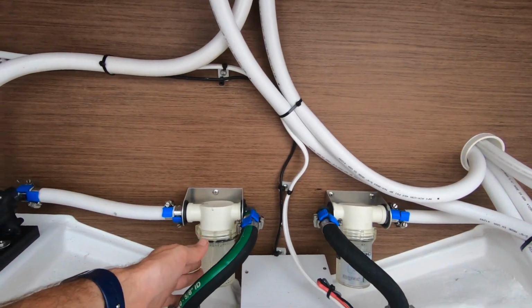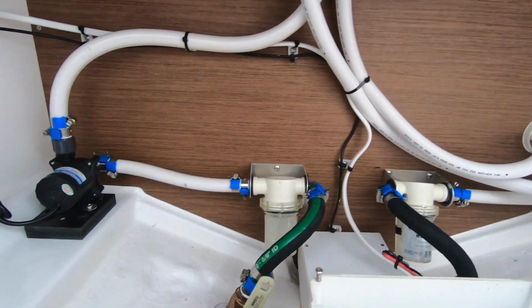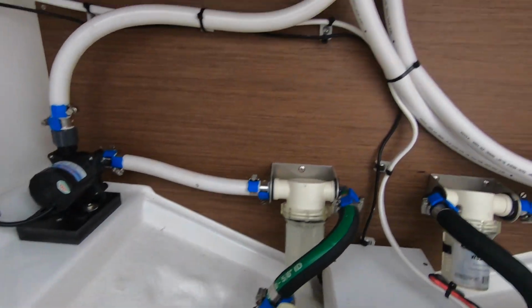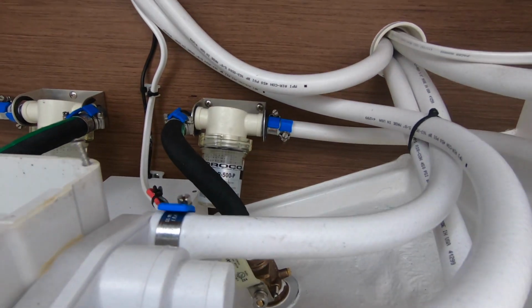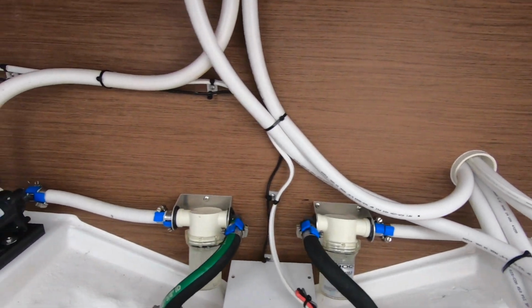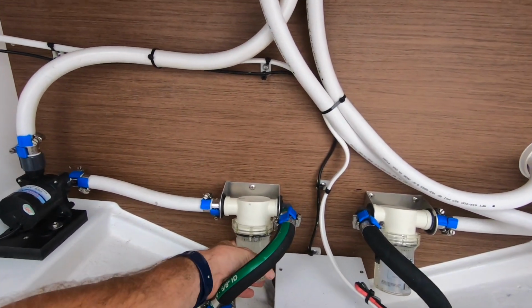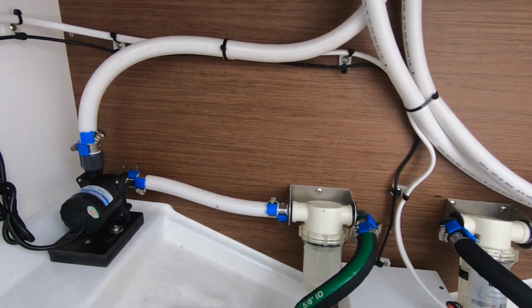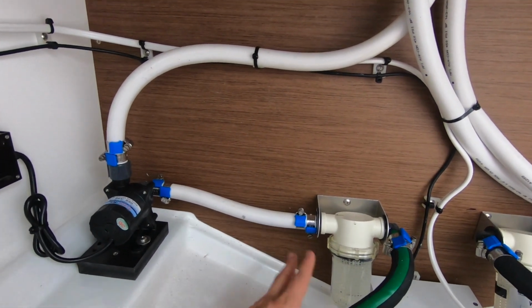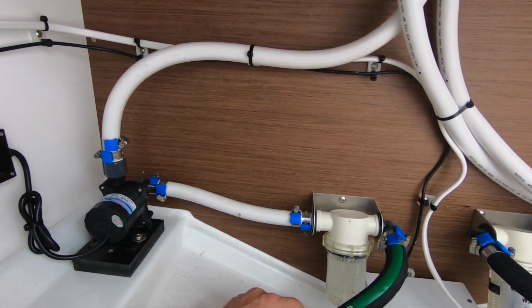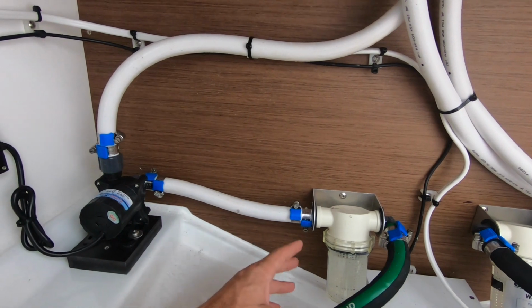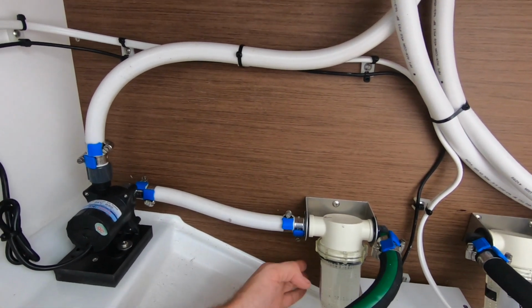We have the two strainers down here, easily accessible, with the valves on either side. You want to check this every once in a while to make sure it's clear. I'd say start off checking once a week, and if you see that it's always clean, go to once a month, and so on, just to make sure the basket isn't obstructed.